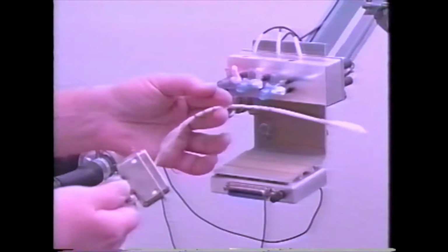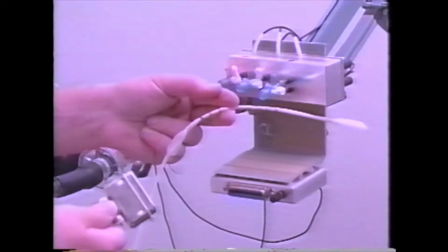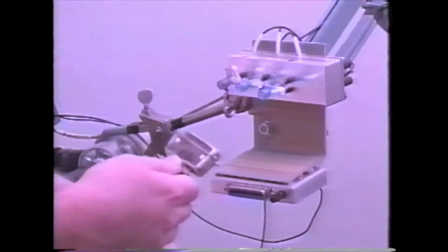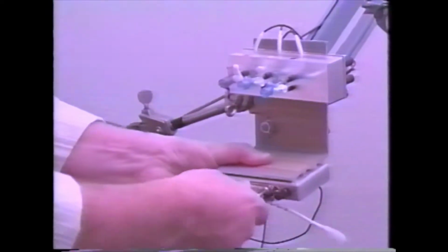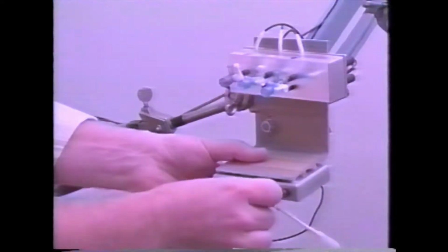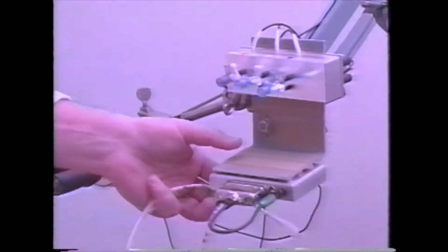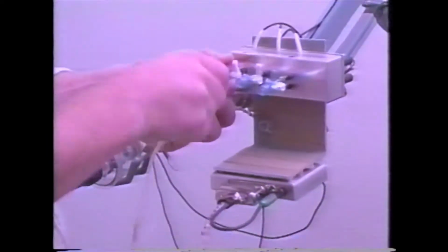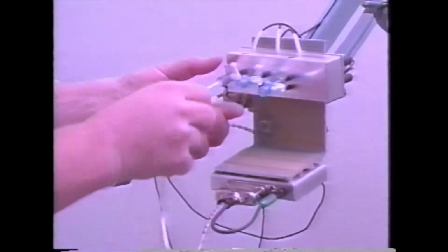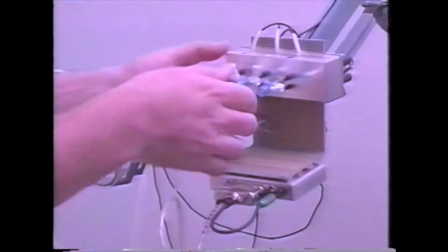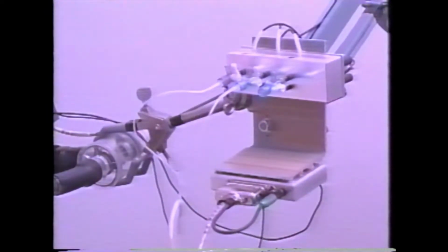The proximal end of the catheter is easily connected to EMG amplifiers and pressure transducers which are placed on the lever. The connector which carries the EMG signals is attached to the EMG amplifier and the shield is grounded. The Teflon catheters which carry the pressures are connected to the pressure transducers for esophageal and gastric pressure. Mouth pressure is fed into the third pressure transducer.